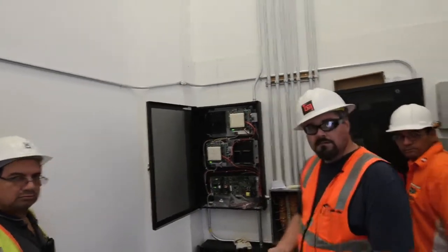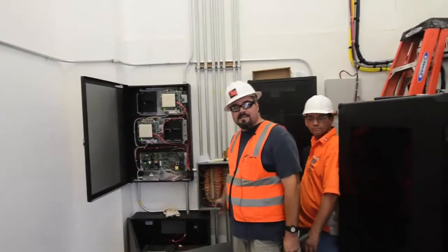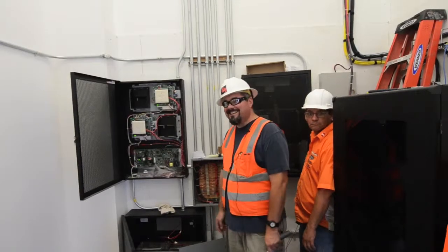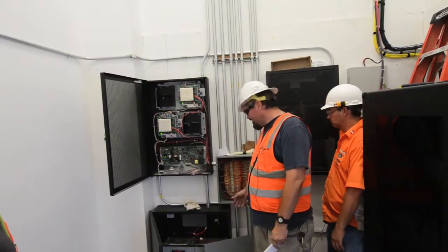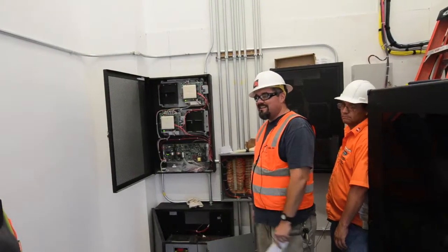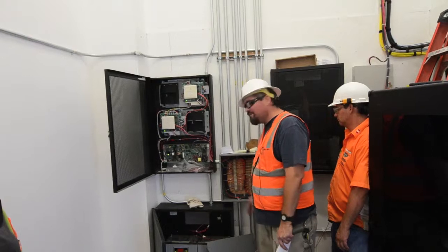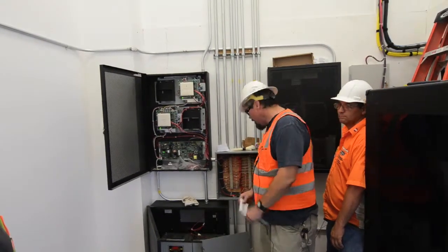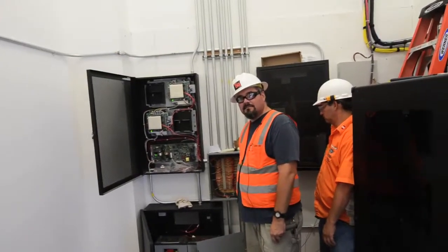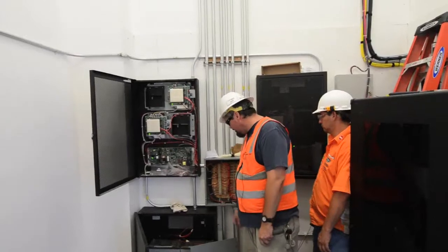So there's nothing in the box that we can mess with, right? Because everything's just tuning. Yeah, this is just basically a big wire nut. That's all it is. But it's a nice looking one. Instead of, you know, back in the day, I remember starting, they had all the wire nuts and they'd shove all the wire in a can and close it and try to figure that out. But at least here it's all nice and looking, it's straightforward, it's labeled, so it's a little easier to work on. It gives you a point to take your meter and start isolating. Yes. Isolate circuits. Lift and isolate. So this is how we always do our fire alarm. It's much easier and better than wire nuts.